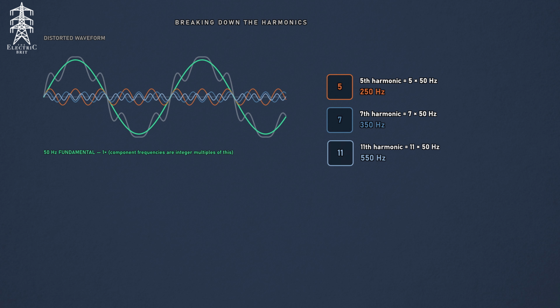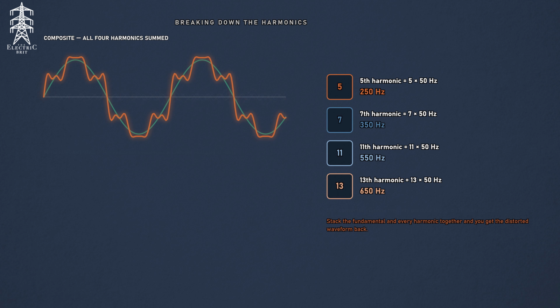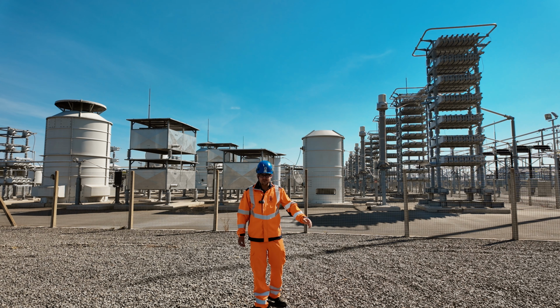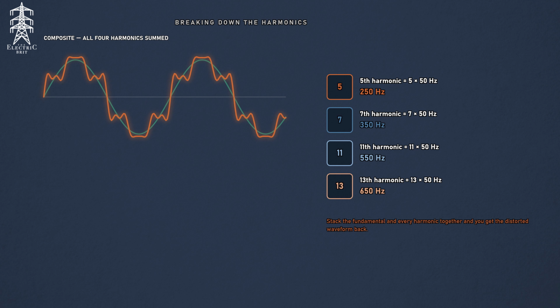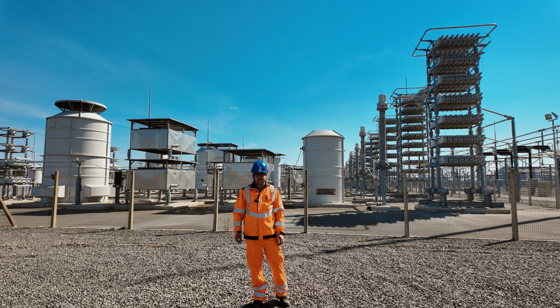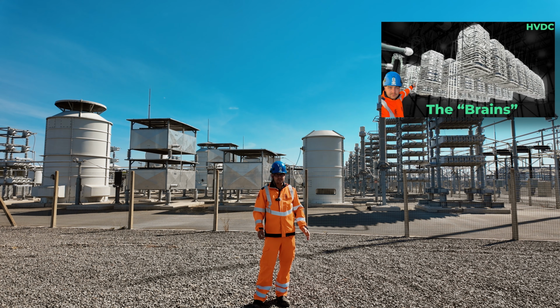Therefore, the seventh harmonic is 350 Hz, and LCC converter stations like this usually produce the 11th and 13th harmonics too, which is why we have these filters behind me. But if you've watched my HVDC video, you'll know LCC converters like this can be 12 pulse bridge to cancel out the 5th and 7th harmonic. If that sounds like gibberish, then I highly recommend watching that video up here.